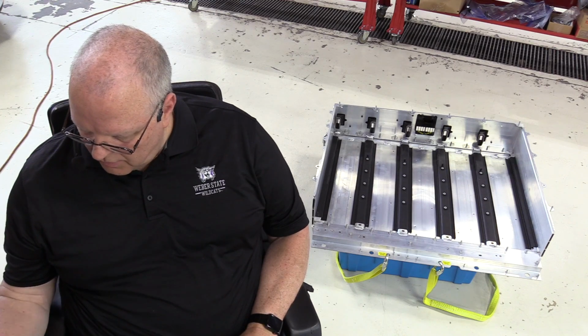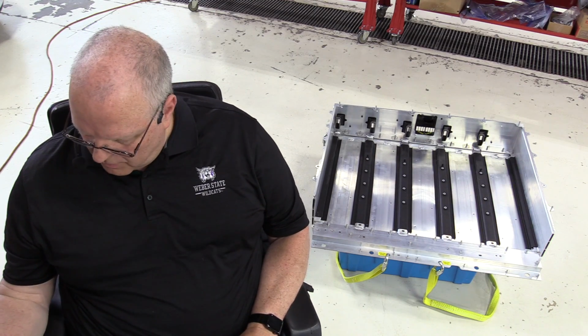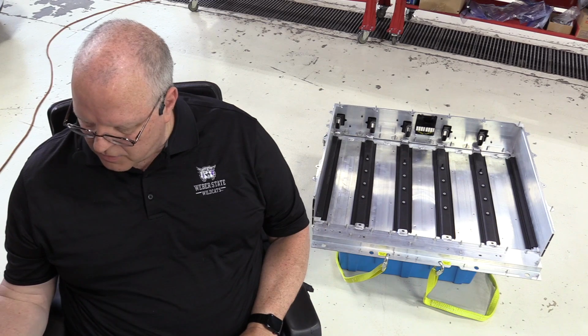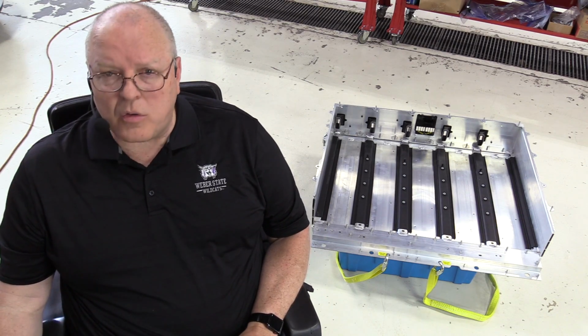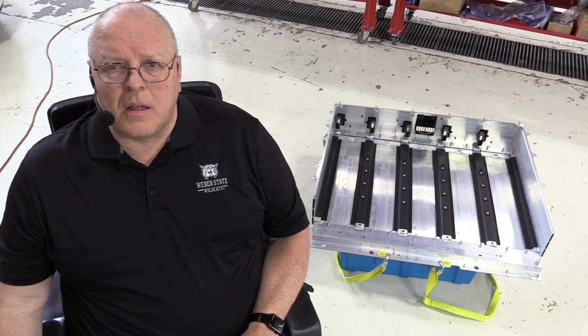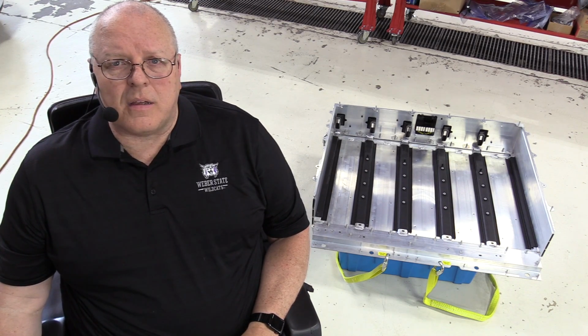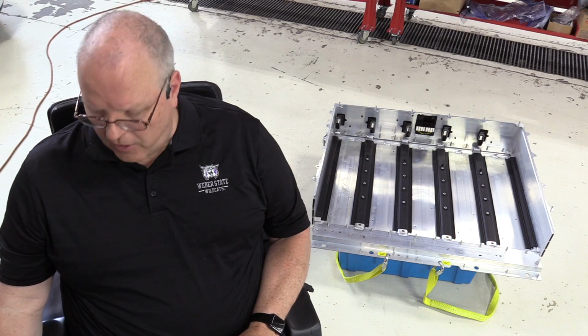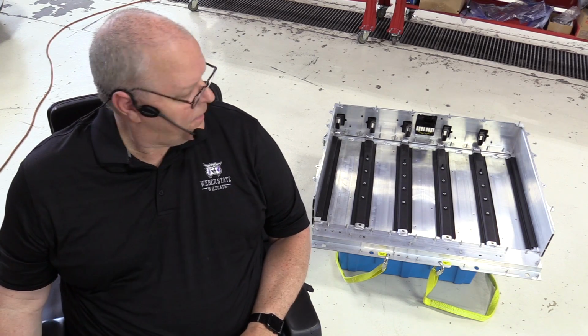At 373 volts, where the charger shut off, if we divide that by 95 cells, that gives us a maximum charge voltage of 3.92 volts per cell. At least yesterday in the shop at pretty warm temperatures - probably 80 to 85 degrees Fahrenheit here in the shop.